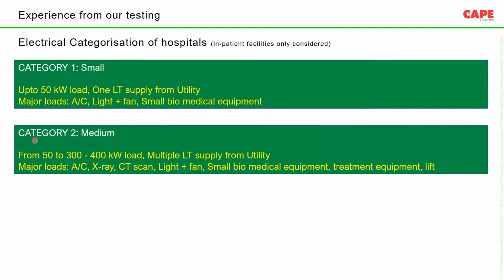Category 2 is the medium type, medium level hospital. This is also a hospital with low voltage supply, but the demand is probably between 50 to 300, 400 kilowatts. Most of the hospitals have multiple LT supplies from the utility. Sometimes there are cases where 5, 6, 7, 8 supplies are taken from different parts of probably one transformer, or sometimes from 2 transformers. So basically, multiple LT supplies are there.